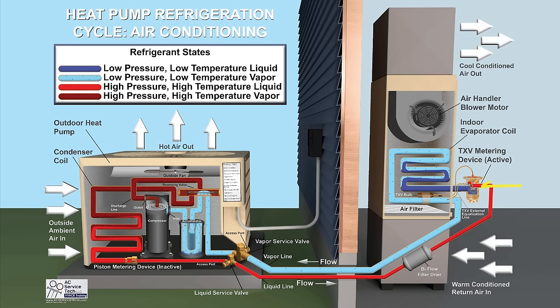There are two main reasons why a coil will freeze. One has to do with the pressure of the refrigerant traveling through the coil, and the other has to do with the amount of airflow — which is actually the amount of heat that is crossing through the fins of this coil.